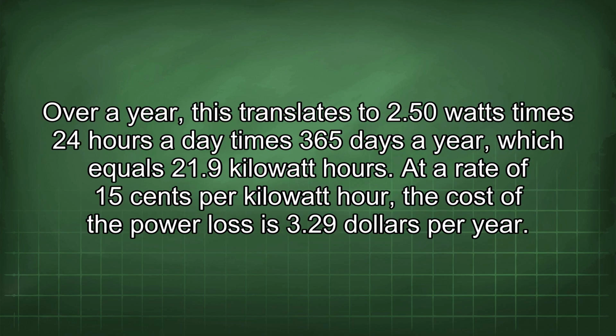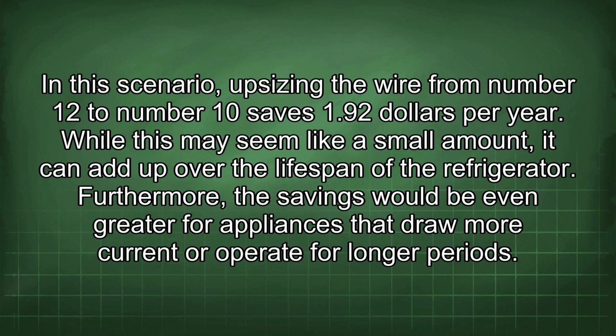Over a year, this translates to 2.50 watts times 24 hours a day times 365 days a year, which equals 21.9 kilowatt hours. At a rate of 15 cents per kilowatt hour, the cost of the power loss is $3.29 per year. In this scenario, upsizing the wire from number 12 to number 10 saves $1.92 per year. While this may seem like a small amount, it can add up over the lifespan of the refrigerator. Furthermore, the savings would be even greater for appliances that draw more current or operate for longer periods.